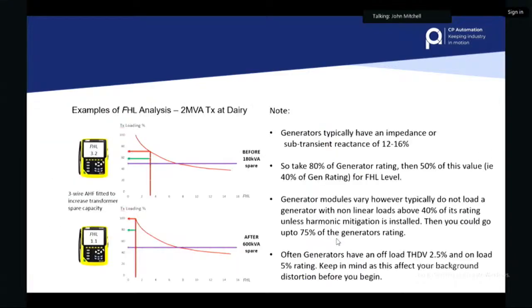Not many people talk about this actually, and here's a prime example of what we've been able to do with many customers now. This is a real life case study. It was a 2 MVA transformer at a dairy, and they only had 180 kVA spare capacity on the transformer when we visited, because they had a lot of harmonics on the transformer. The current harmonics are causing distortion in the transformer and derating the transformer. So the voltage distortion goes up and the transformer's rating of power goes down. We installed an active harmonic filter onto this system, and we released 600 up. We pushed them back up to 600 kVA spare capacity, which meant they could add the additional loads they were planning for instead of buying a bigger connection from the grid and a bigger transformer.